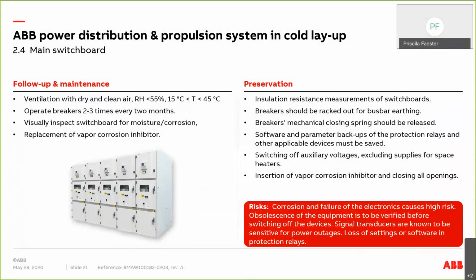For follow-up and maintenance, it's good to operate the breakers 2 to 3 times every 2 months, so that there is movement in the mechanical parts of the breakers. Otherwise, it's more like a visual inspection for moisture and corrosion, and the replacement of vapor corrosion inhibitors when possible, or when needed.